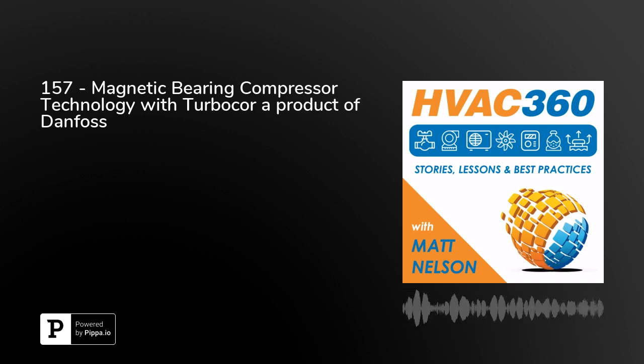There are some differences whenever you're talking about designing with a Turbocor compressor. One difference is that you can have a much lower superheat because we don't have oil in the compressor. You don't have to worry about liquid return that could flush out anything. But for the most part, there are some other differences.